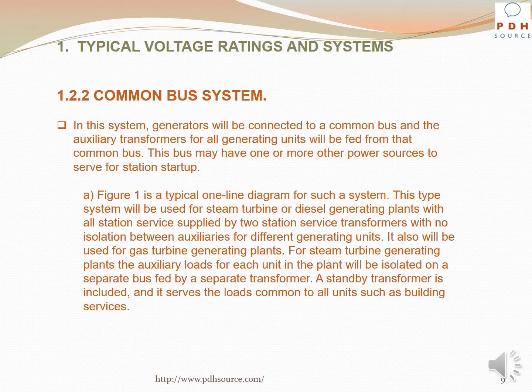For steam turbine generating plants, the auxiliary loads for each unit in the plant will be isolated on a separate bus fed by a separate transformer. A standby transformer is included and it serves the loads common to all units, such as building services.